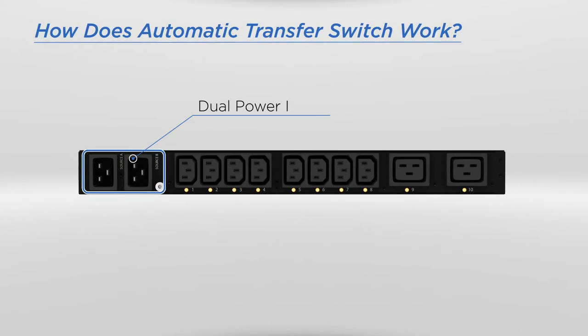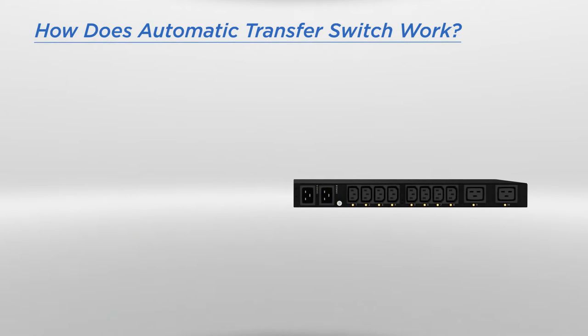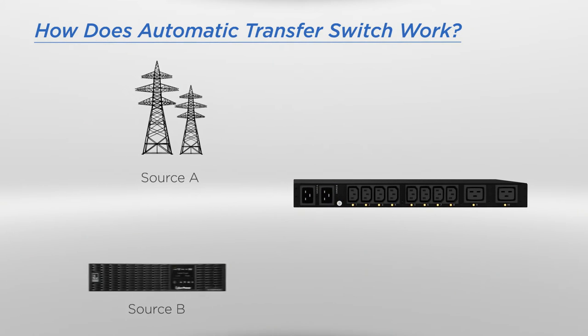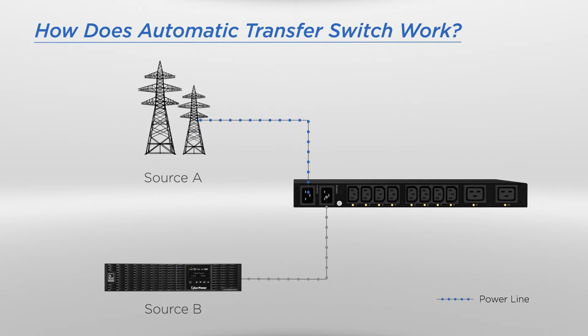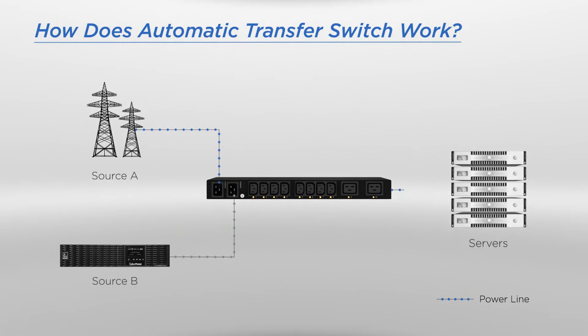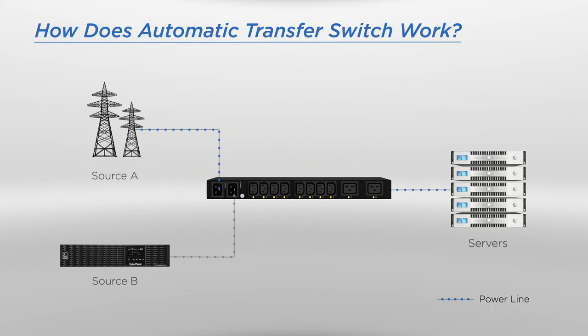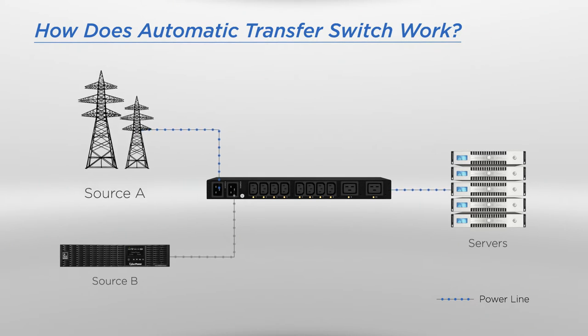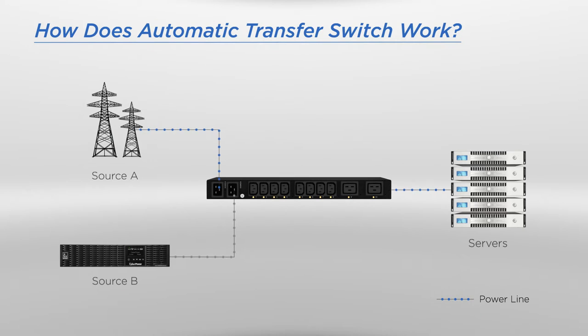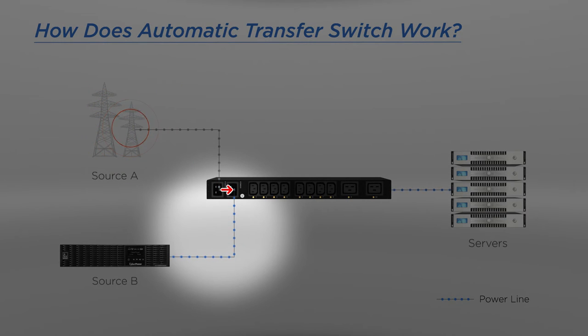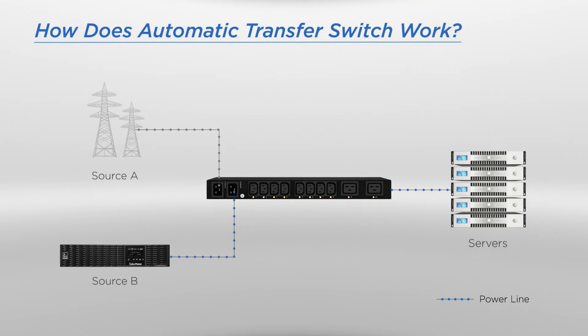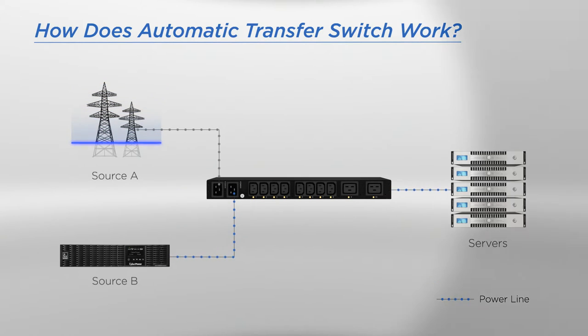With dual power inputs, ATS can connect to two AC power sources simultaneously, including the utility grid, a generator, or UPS system, and distribute power to multiple devices. The flexible ATS allows users to select their preferred input power source. When preferred source A becomes unstable or fails, the ATS will automatically switch to source B without interrupting the operation of loads. Once preferred source A becomes stable or recovers, the ATS will switch back.